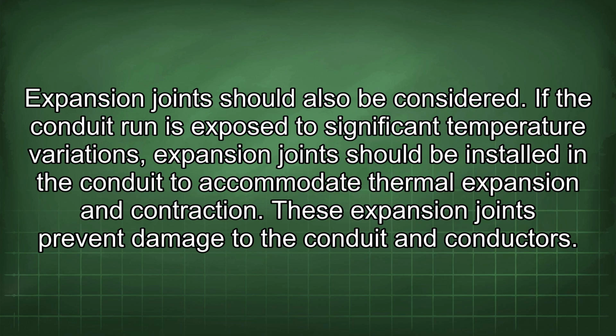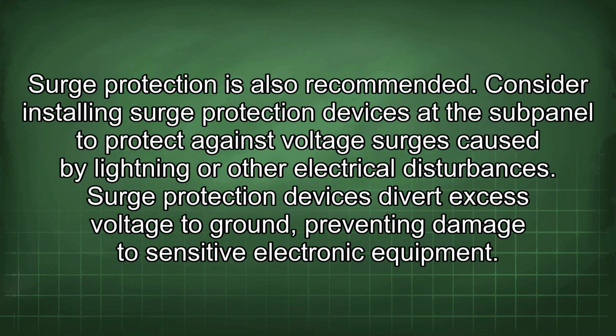Expansion joints should also be considered. If the conduit run is exposed to significant temperature variations, expansion joints should be installed in the conduit to accommodate thermal expansion and contraction. These expansion joints prevent damage to the conduit and conductors. Surge protection is also recommended. Consider installing surge protection devices at the subpanel to protect against voltage surges caused by lightning or other electrical disturbances. Surge protection devices divert excess voltage to ground, preventing damage to sensitive electronic equipment.